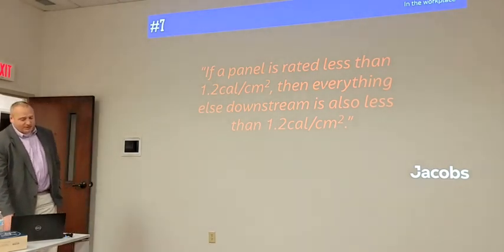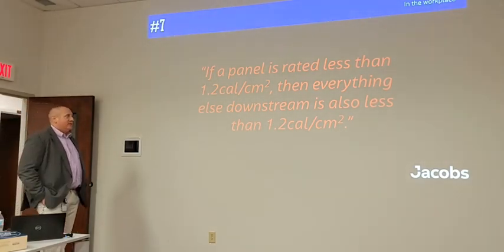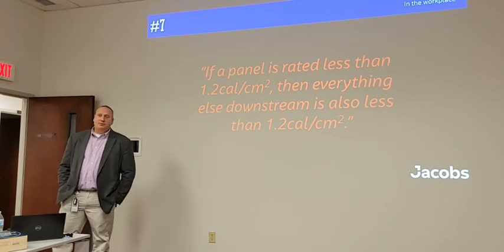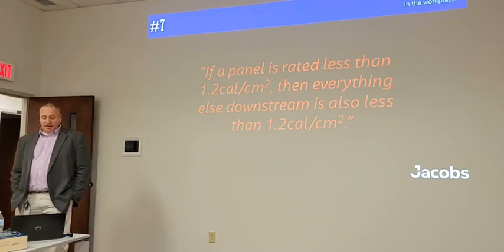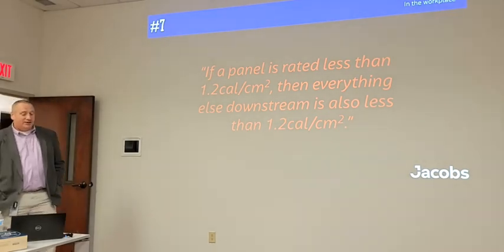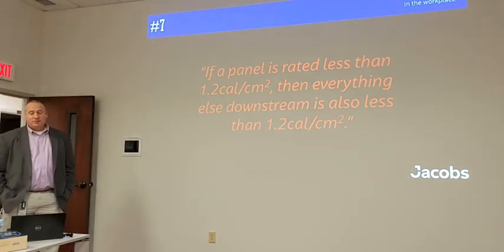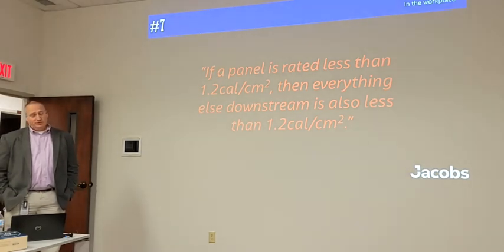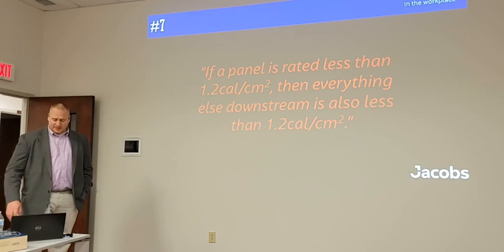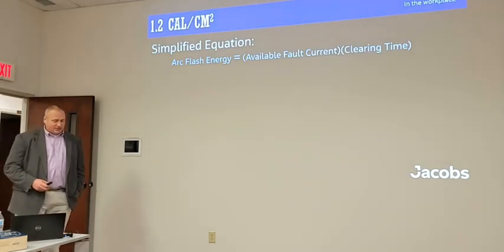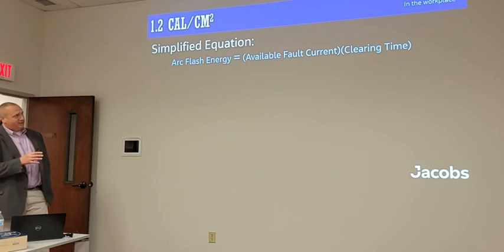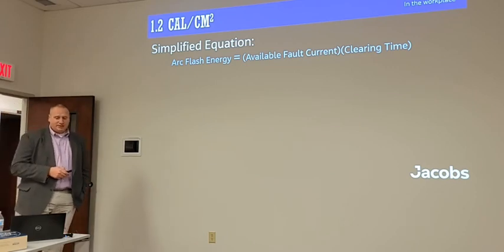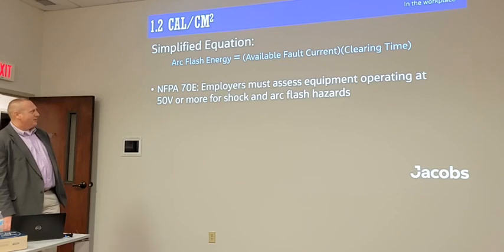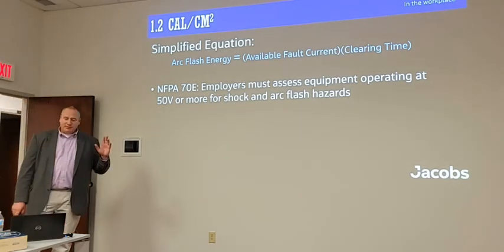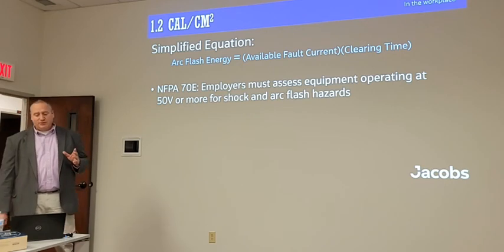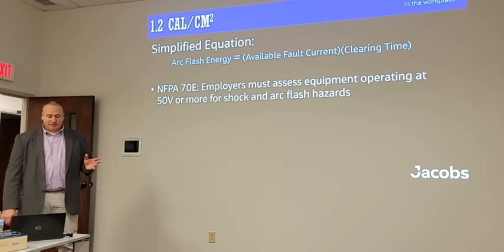The next one is if a panel is rated at less than 1.2 calories per centimeter squared, then everything else downstream is also less than 1.2 calories per centimeter squared. Now, that was one that even I was guilty of in a lot of scenarios, assuming for a while, until I started thinking it through and playing around with some of the arc flash software and realized that it's not necessarily true. It goes back to this equation of available fault current times the clearing time is what determines our arc flash energy level. And the 70E does have a requirement that employers must assess any equipment 50 volts or more for shock and arc flash hazards to begin with, so we need to analyze it.